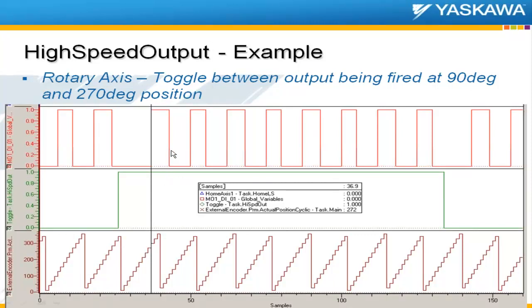The off time is set at about 20 milliseconds, so that varies a little with the task rate. When the toggle input goes off, it immediately changes the target to 90 degrees. Since the axis was already past 90 at that moment, it waits until the next time it crosses 90 degrees and then turns on again.